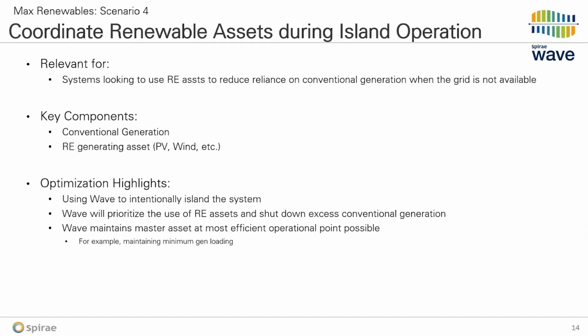So in this scenario, we'll take a look at the intentional island capability that Wave can bring to your microgrid. It allows you to do planned island transitions, smooth transitions when you have information about when there might be instability in the grid, or it's just in your best interest to operate on your own in the weak grid scenario. To show that capability, once we're islanded, we'll be taking advantage of renewable energy as it becomes available and backing off our conventional generation. So Don, maybe we can switch over and take a look at that if you're ready.